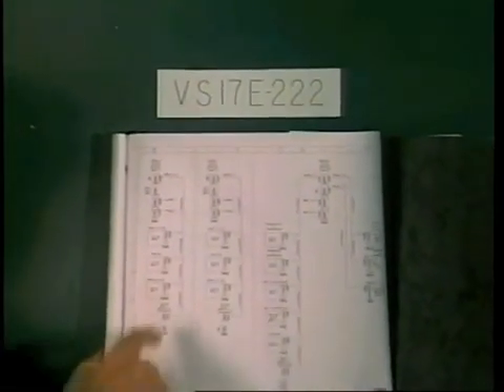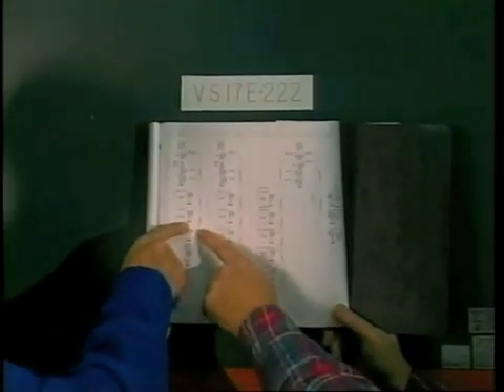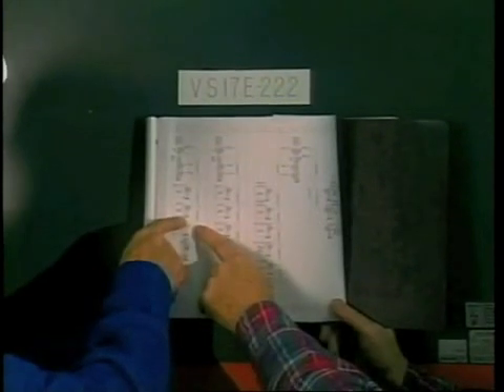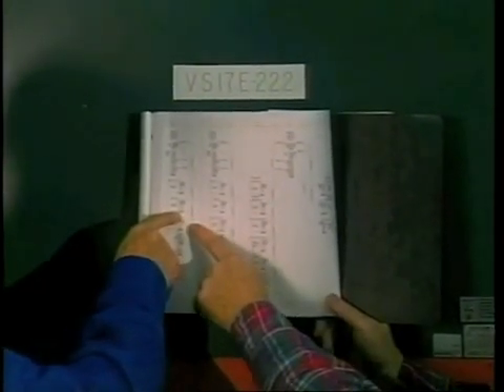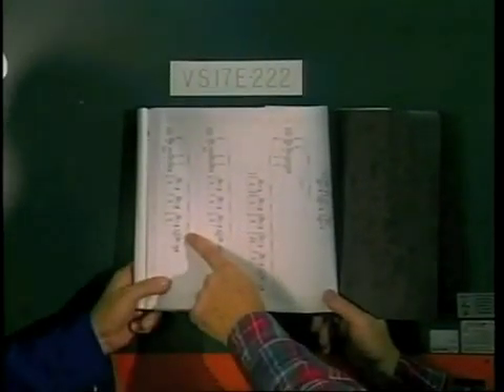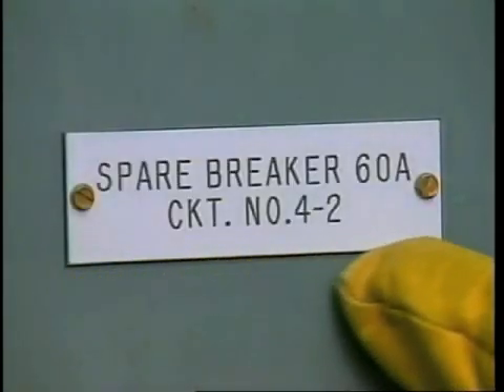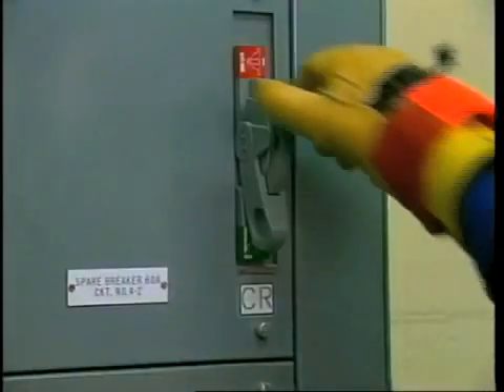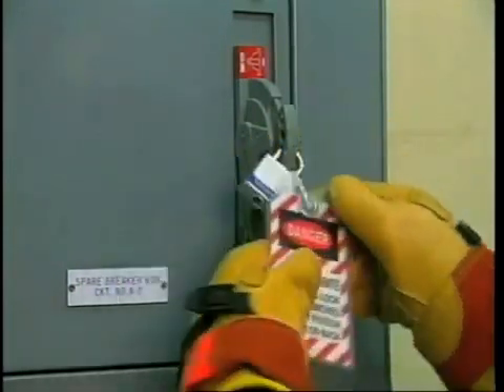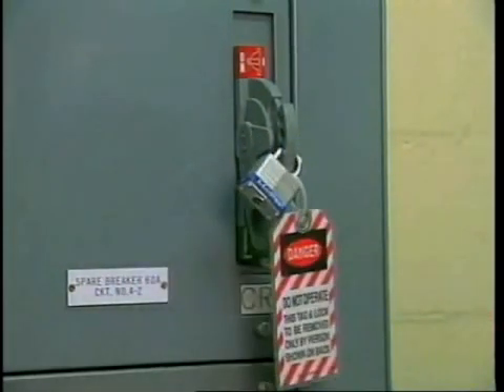All equipment must be clearly labeled and accurate. Up-to-date one-line diagrams must be available for safe work on this equipment. And be sure you're working on the correct equipment. Identify, test, lock, tag, and try all remote sources of energy before work is done on a motor control center. Be sure that all mechanical interlocks have functioned properly.